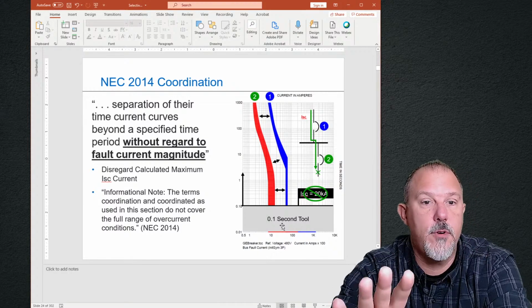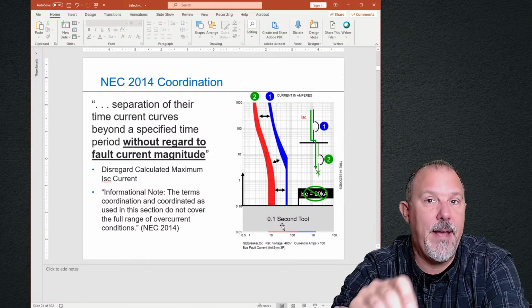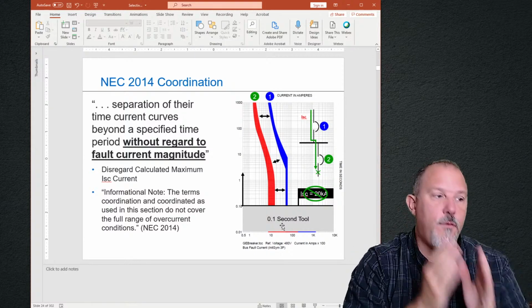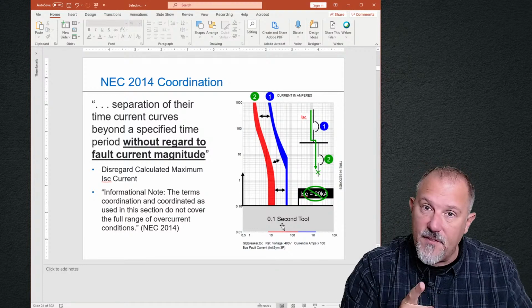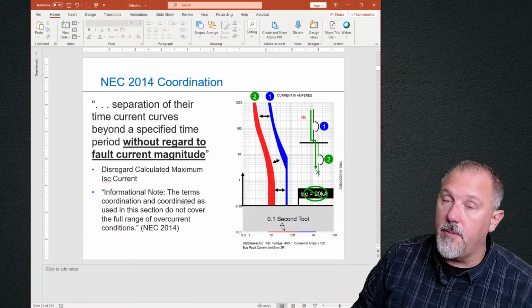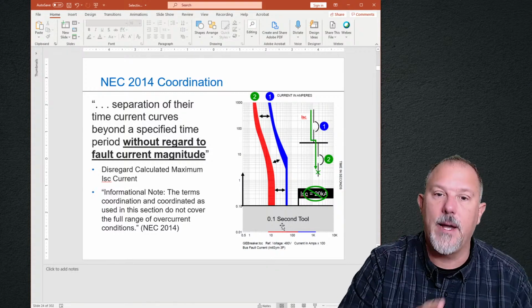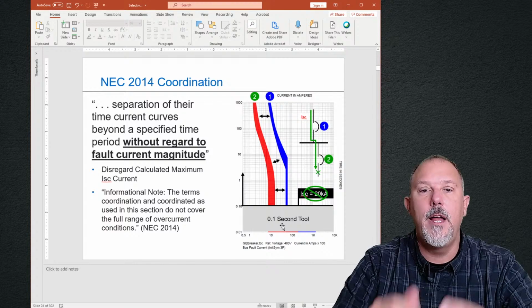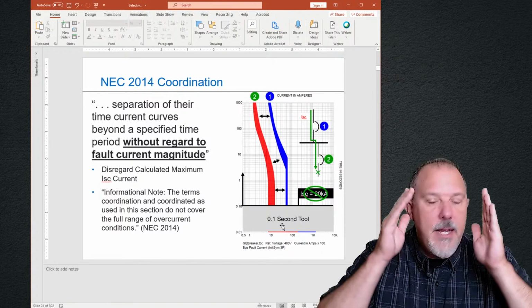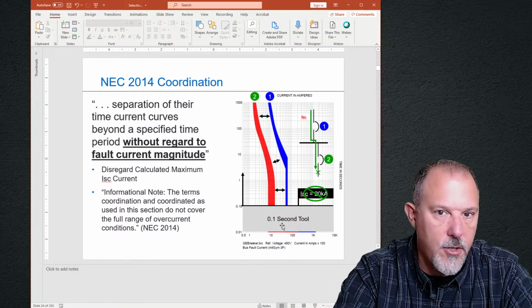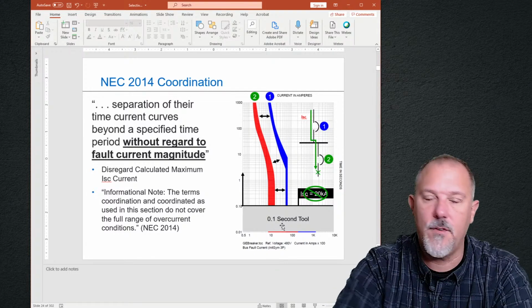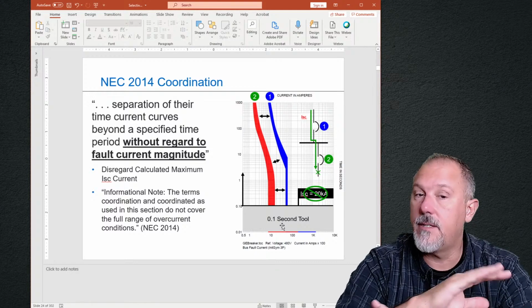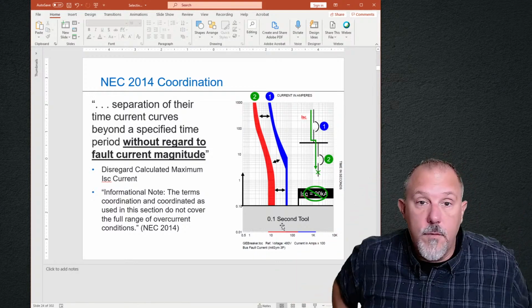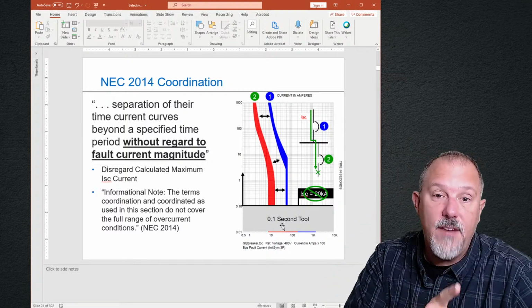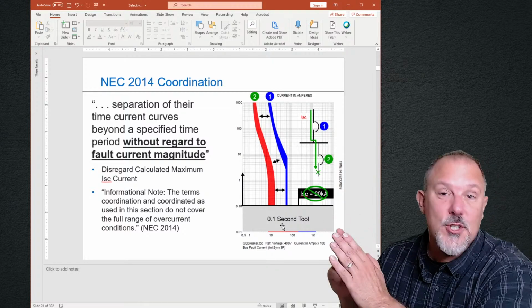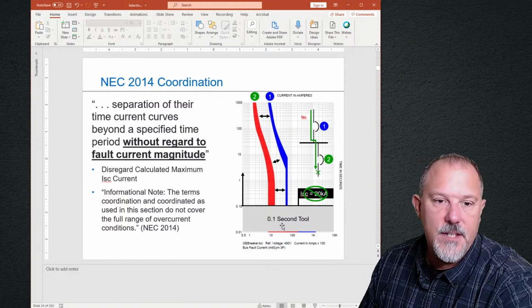And we just ignore that fault current because it says without regard to fault current magnitude. So I don't have to compare the performance of overcurrent protective devices with regard to it. I don't have to. I can elect to. I can always go above and beyond bare minimum requirements of the National Electrical Code, but I don't have to. I can ignore the fault current. I can hide everything below 0.1 seconds and look for separation of curves above 0.1 seconds. I may know for a fact that if a ground fault current or a bolted fault current occurs and they both see it, that they will both open. I can know that for a fact, but I'm not required by code to address it. I just need to make sure that I coordinate in the overload region of those two trip curves. Now, could I have a fault current that is lower than that instantaneous pickup and these actually selectively coordinate? Yes, I could. Likelihood of that is very low, but I could.